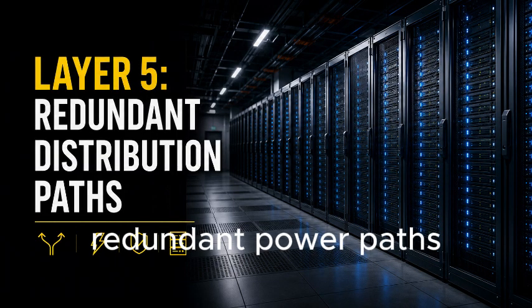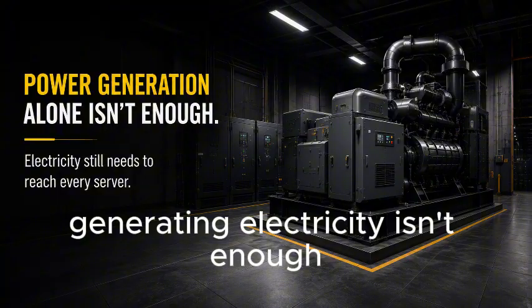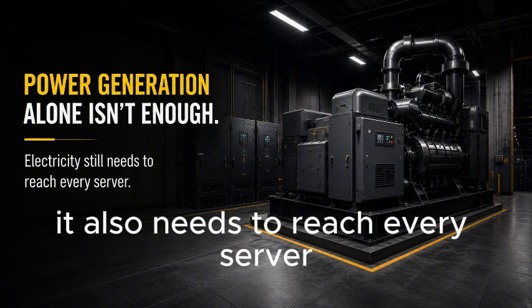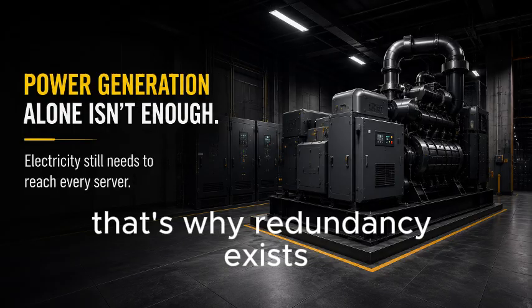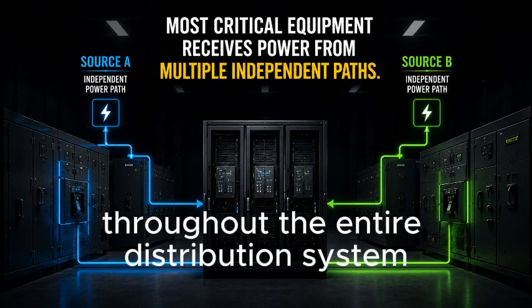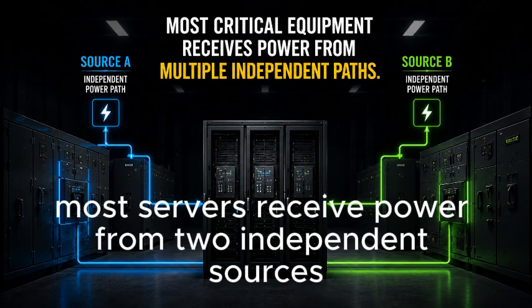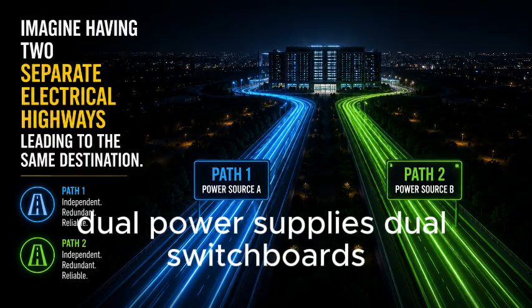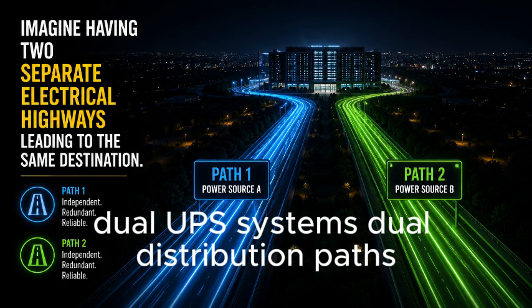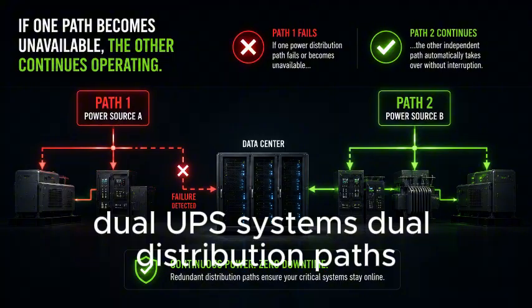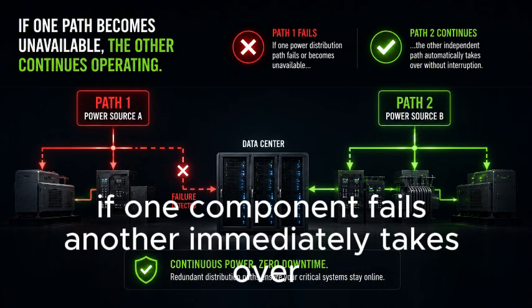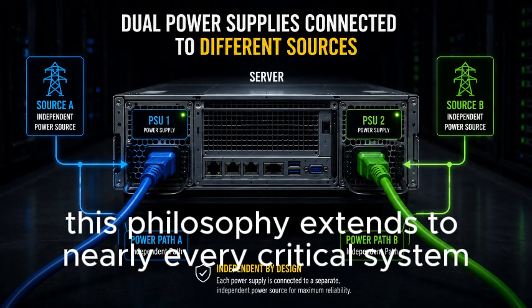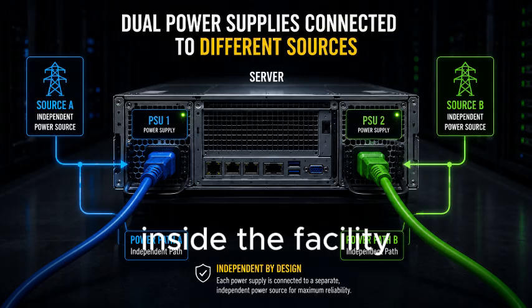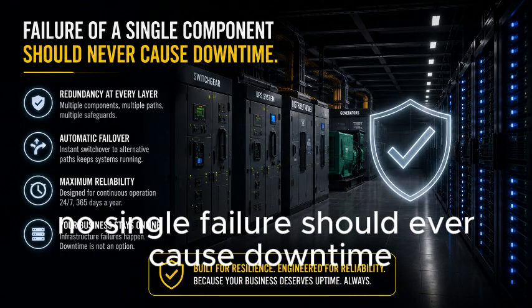Redundant power paths. Generating electricity isn't enough. It also needs to reach every server. That's why redundancy exists throughout the entire distribution system. Most servers receive power from two independent sources: dual power supplies, dual switchboards, dual UPS systems, dual distribution paths. If one component fails, another immediately takes over. This philosophy extends to nearly every critical system inside the facility. No single failure should ever cause downtime.